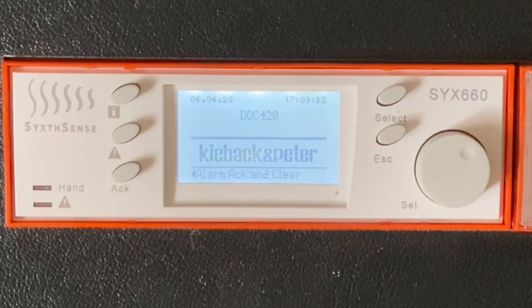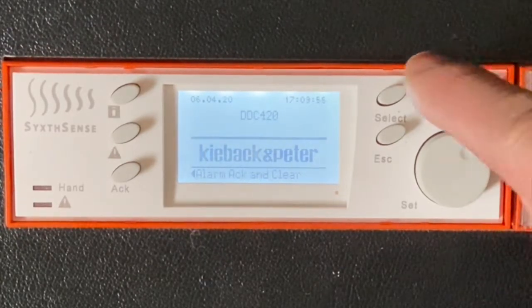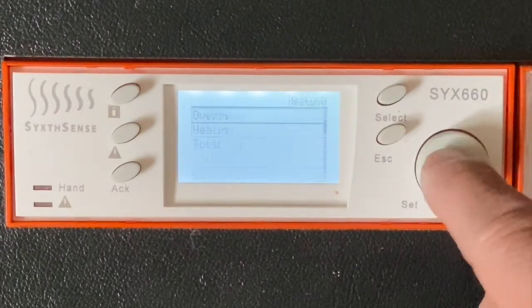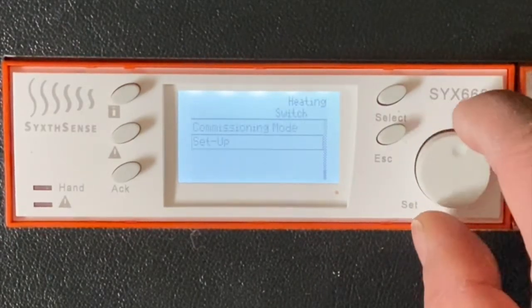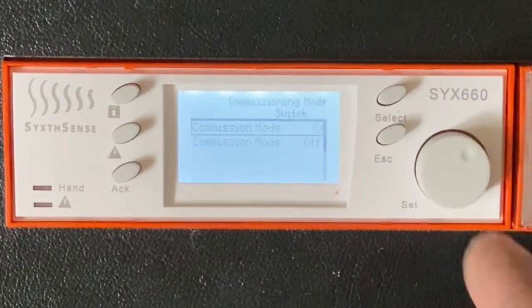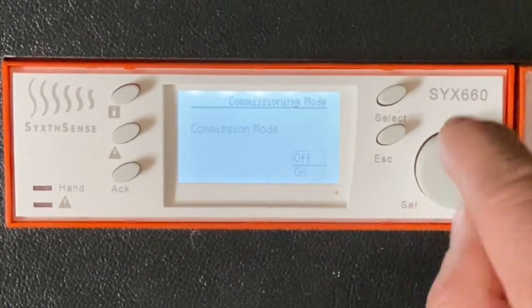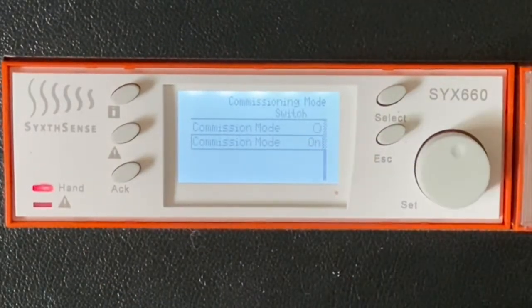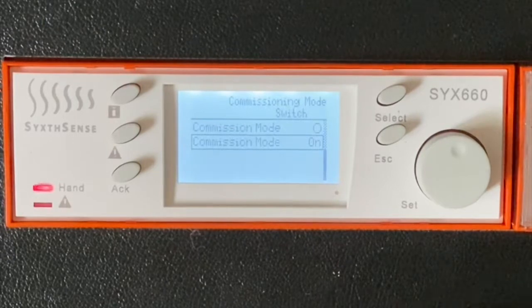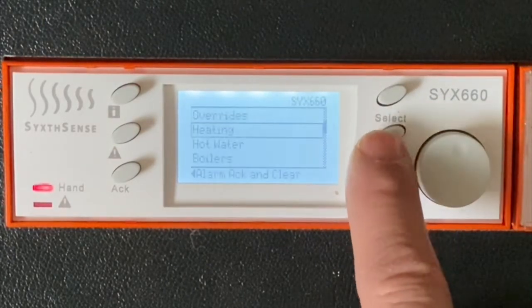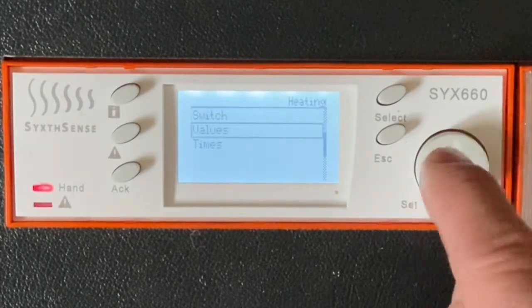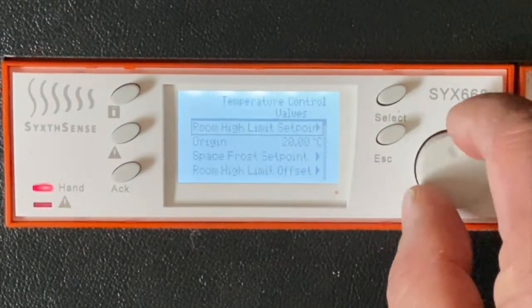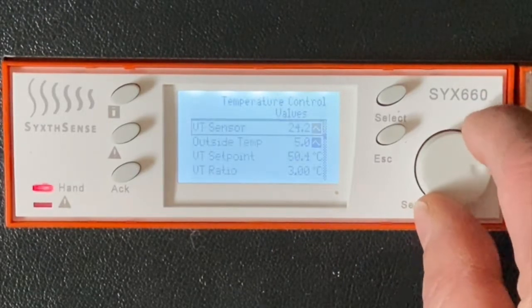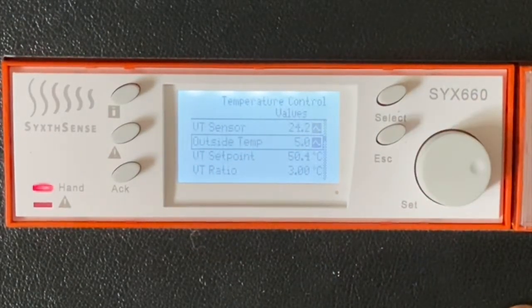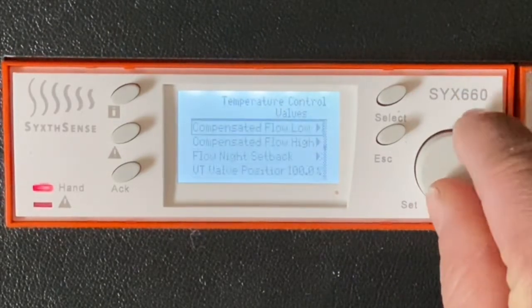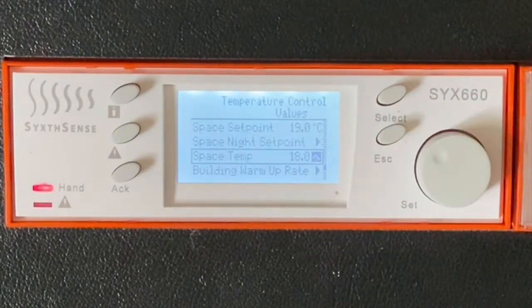So the commissioning mode simulates a winter's day, and to put it into commissioning mode, you press the select button, you choose heating and switch, and in that list you then choose commissioning mode, and then you turn the commissioning mode on. The hand light will come on and the display will start to flash at you to say commissioning mode is active. Now what that actually does, if we come out of the switch function and go back into heating and choose values, and then look at temperature control, if we just scroll down the list of values there, the outside air temperature is now simulated as being 5 degrees, and the space temperature is now simulated as being 18 degrees.